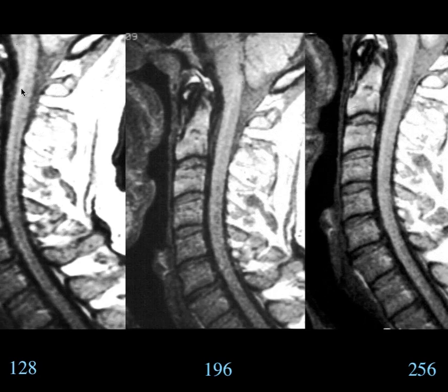And that was first concerning, that it could be the central canal of the cord, but it turns out that's just an artifact if you don't have enough phase encodings. You go to 192, we can see that we have a nicer image, a little bit sharper image of the cord. And if you go up to 256 phase encodings, we even get a sharper image, and we can see the details of the cord structure better at the 256 image.